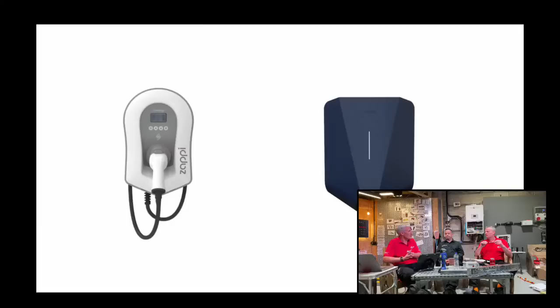So all we're saying is, if we're in favour of this, we want that to go on - if it meets that standard, we'd be happy for it to be built into the EV charging unit itself. Yes, and you wouldn't need an RCD upstream, but you do need to bear in mind the protection for the wiring. So if it's buried in a wall, or it's a TT system, of course you'd need an external RCD.